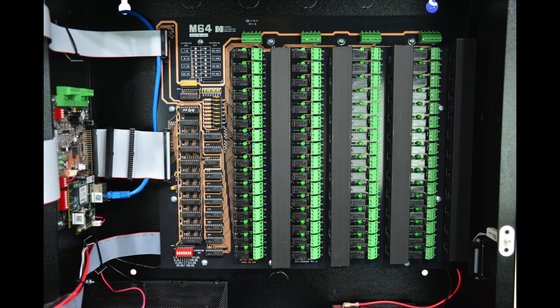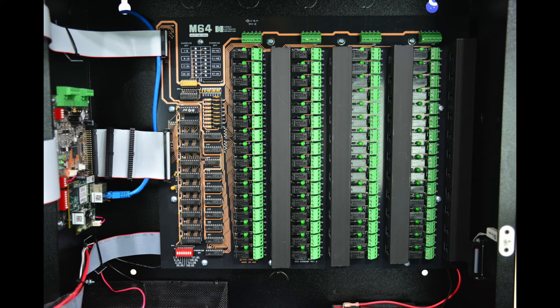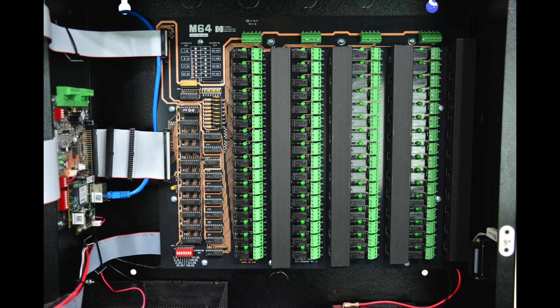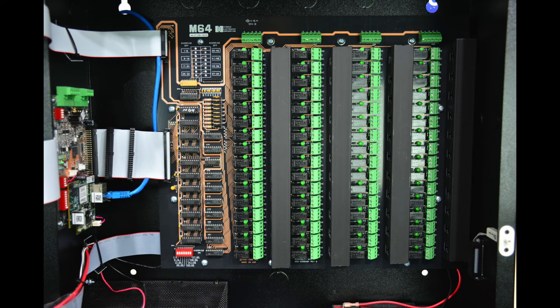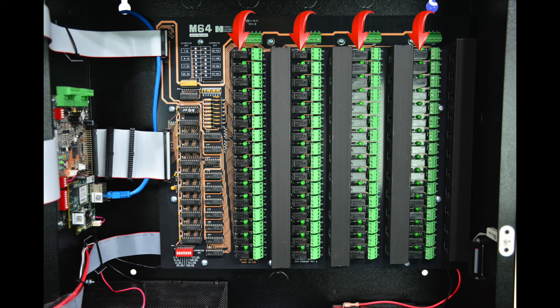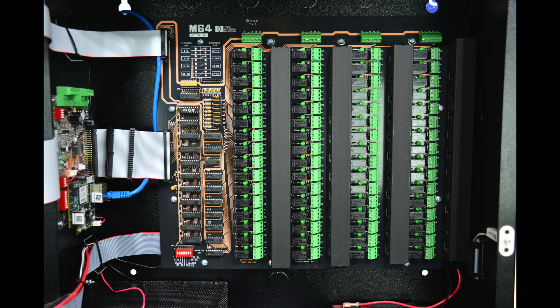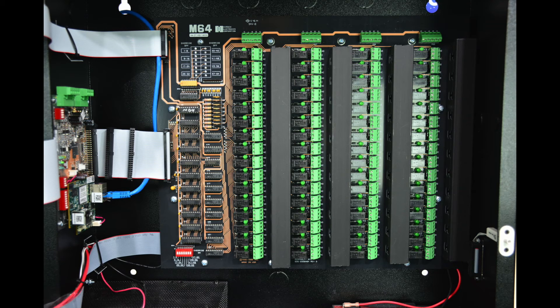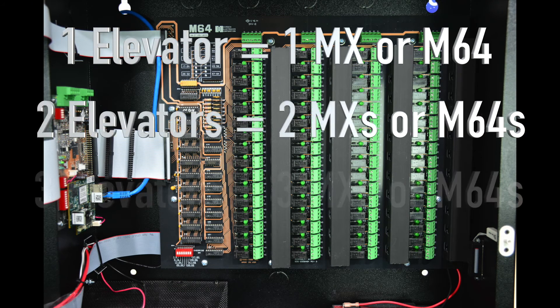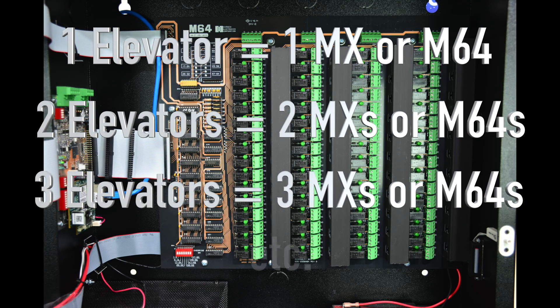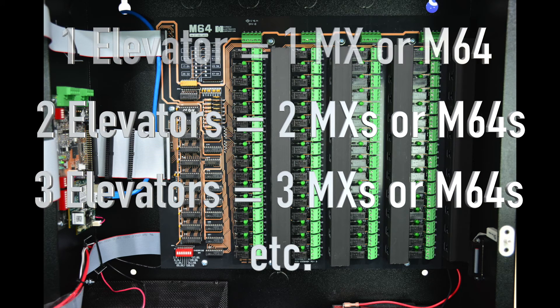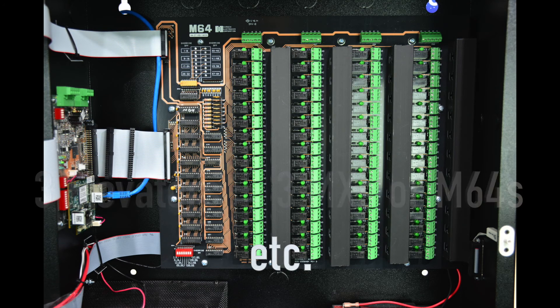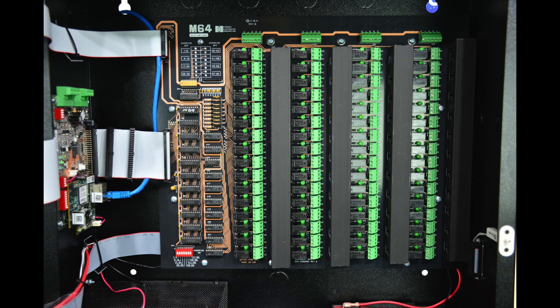The main board for the M64 has four columns of 16 outputs for a total of 64 outputs. Like on the MX, each output is electronically fused and also field replaceable. It is important to note that when you are planning for elevator floor control, that you plan one MX or M64 per elevator bank, and do not do more than one bank on a single MX or M64. So one bank, one MX or M64, two banks, two MXs or M64s, and so on.